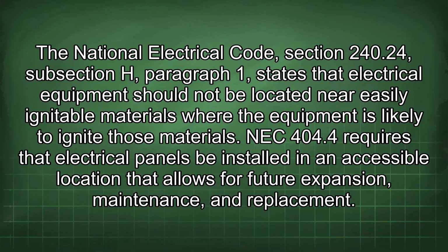National Electrical Code, Section 240.24, subsection H, paragraph 1 states that electrical equipment should not be located near easily ignitable materials where the equipment is likely to ignite those materials. NEC 404.4 requires that electrical panels be installed in an accessible location that allows for future expansion, maintenance, and replacement.